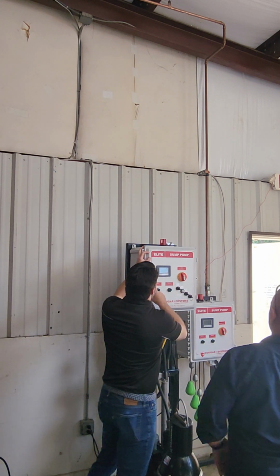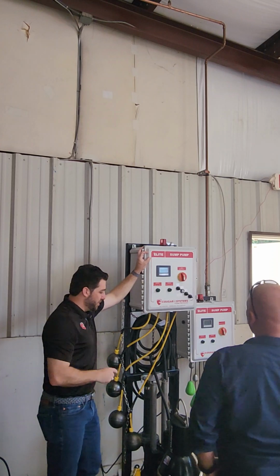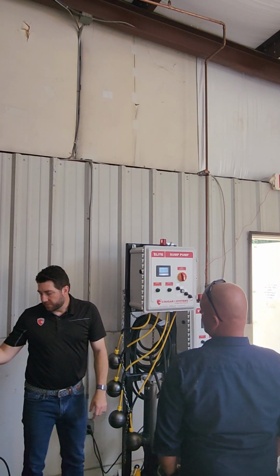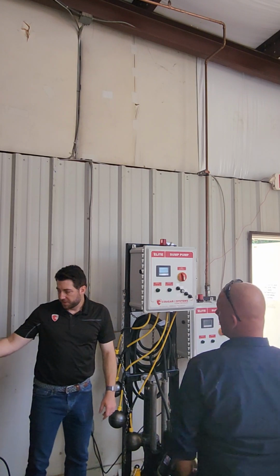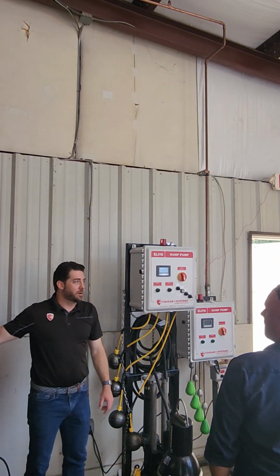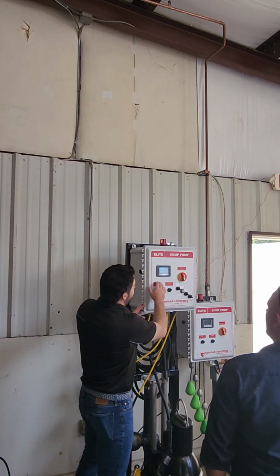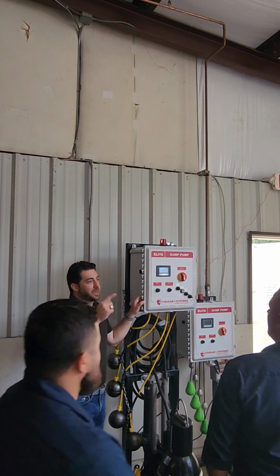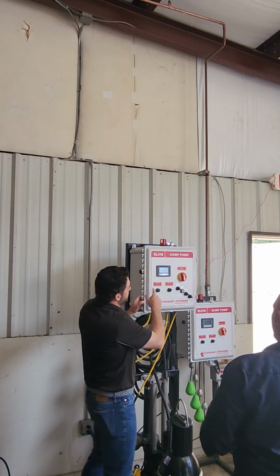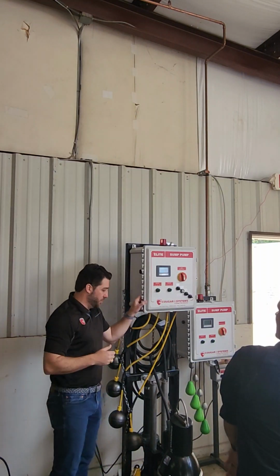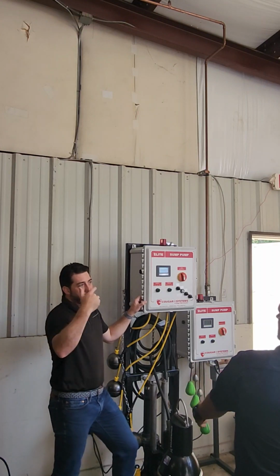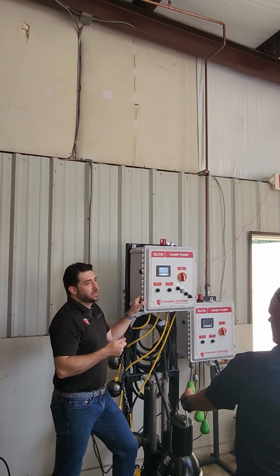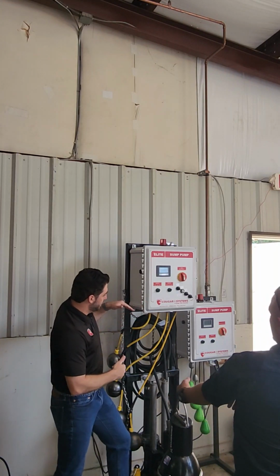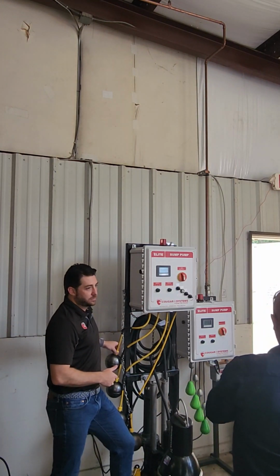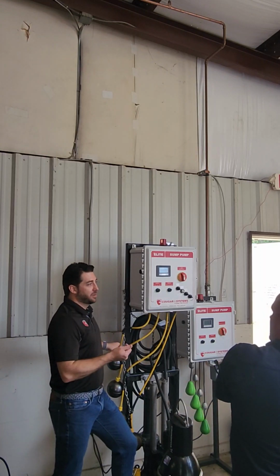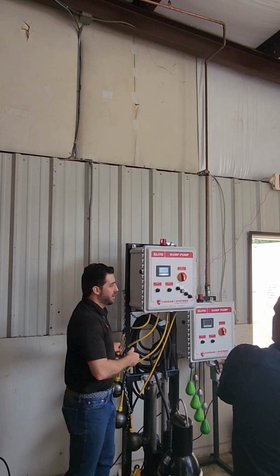The lag pump. So this is an alarm that we've added in. So we talked about how in this traditional 4-float switch assembly, you don't get your high level alarm until both pumps fail. Okay, the lag pump counter on this one is going to keep track of how many times your lag pump came on. And so you can set that for as low as 2 or 4 or 5, whatever you want. But that's going to keep track of every time that your lag pump comes on in that sequence, and then it's going to alarm. So this is a good way that you can keep your high level alarm as the top float switch, but get an alarm if your lag pump is running. Okay, so we'll show you how that can happen.